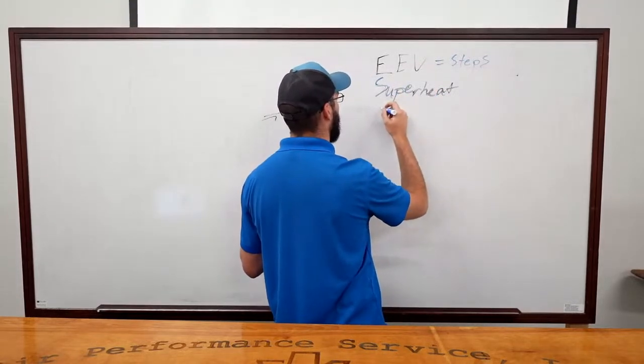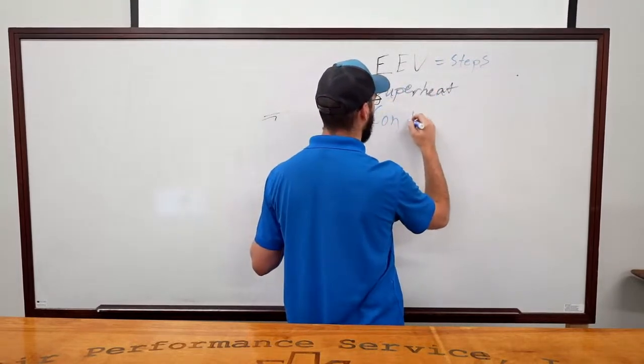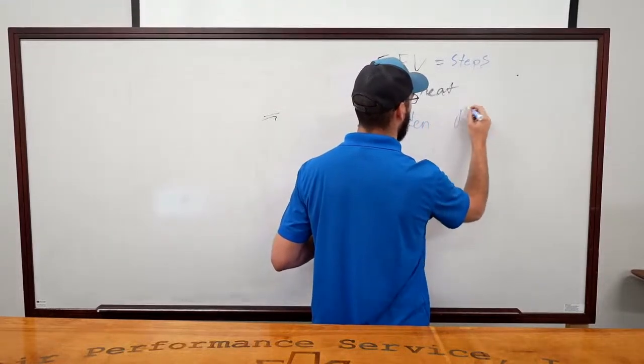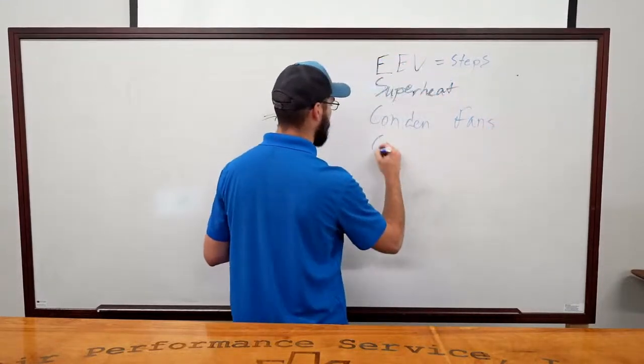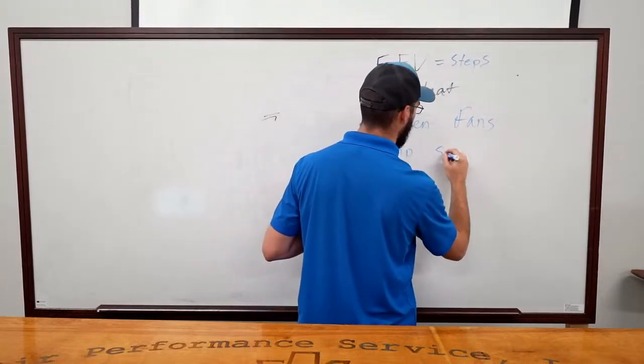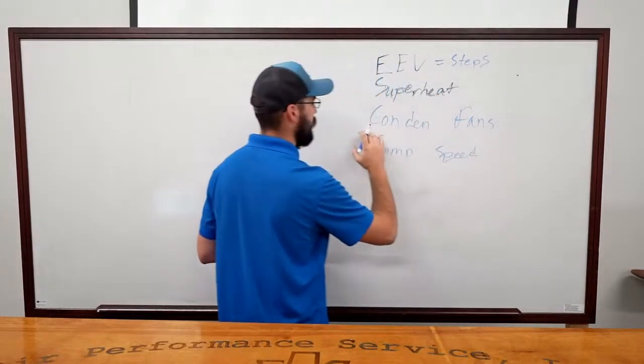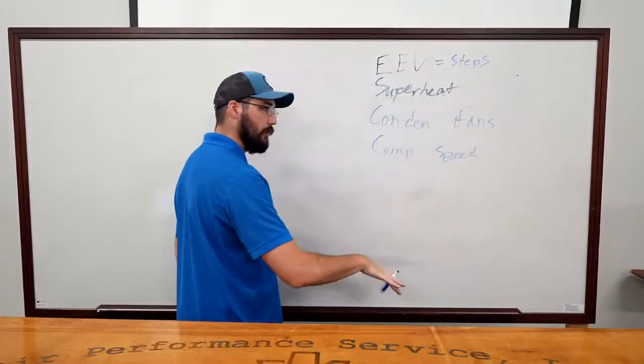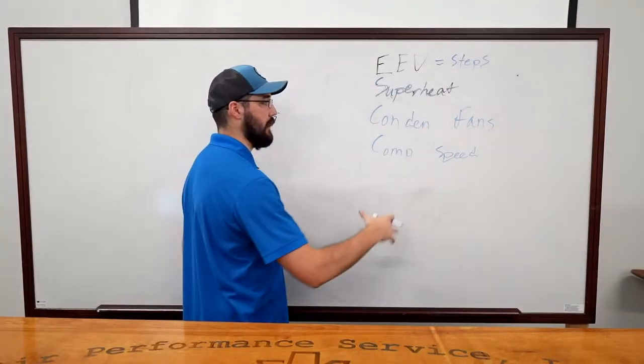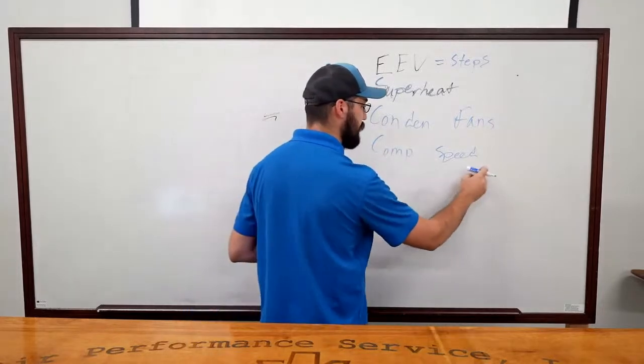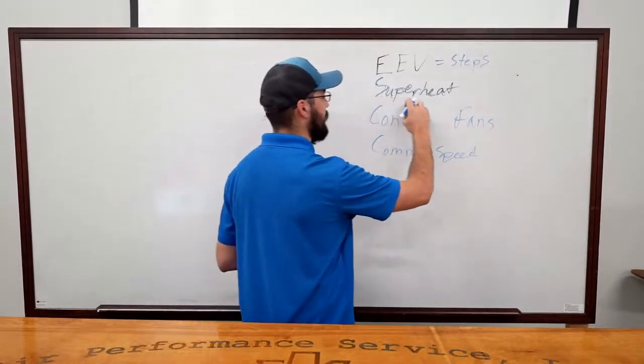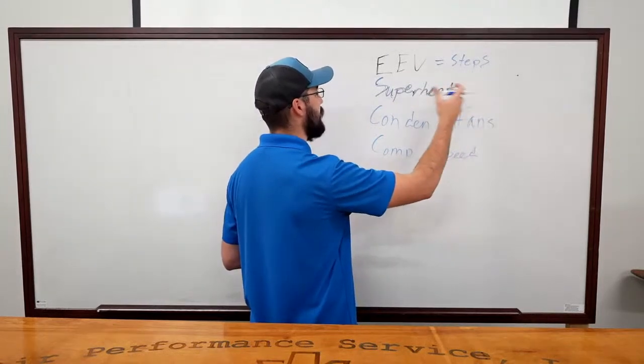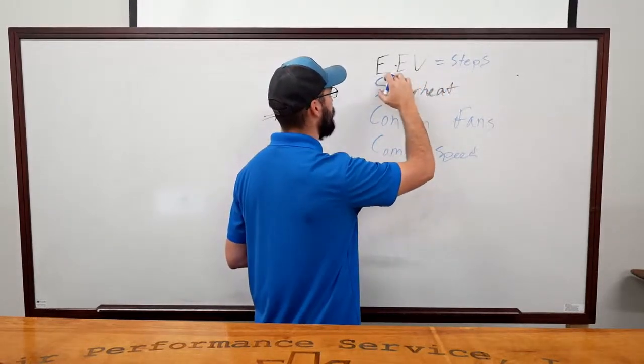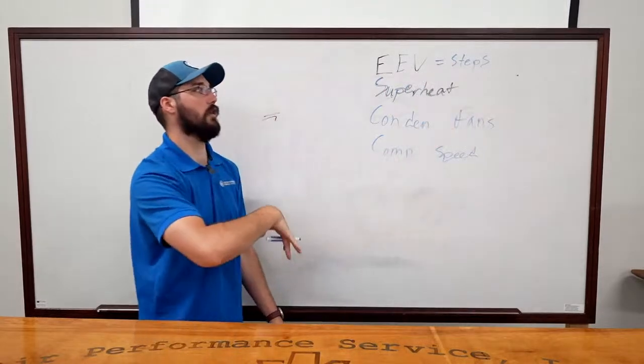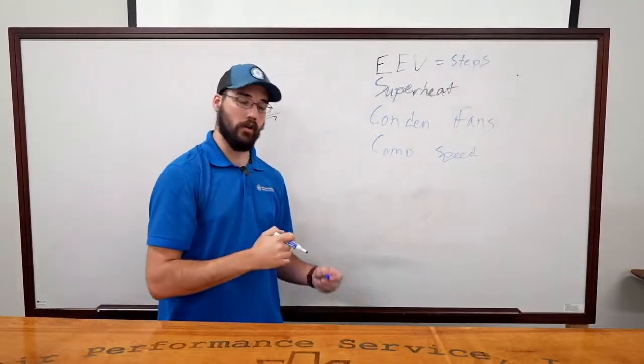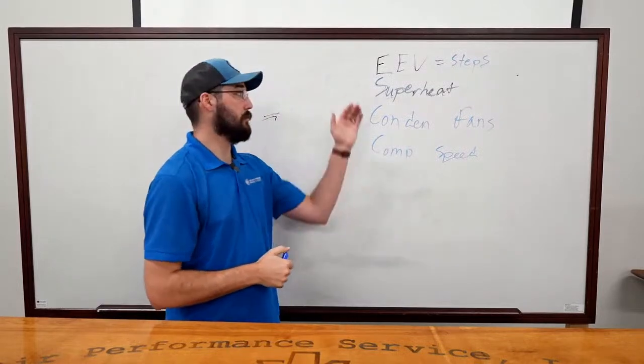We can also look at our condenser fans and our compressor speeds. So if the condenser fans are ramped down, they're not having to reject a lot of heat. Our head pressure is down. Our compressor speeds are down. We have excessive superheats at several of our boxes or our fan coils, and our EEVs are mostly, if not all the way, open. These are the symptoms you're going to start to see.